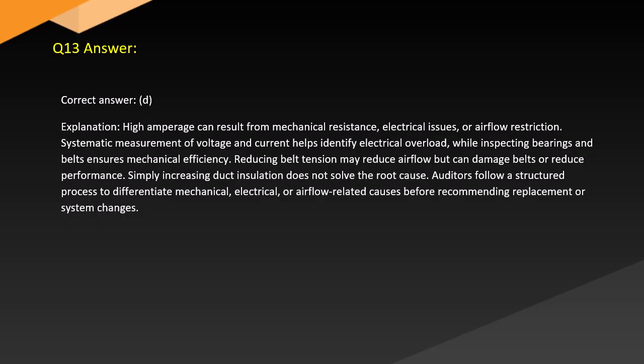Answer. Correct answer, D. Explanation. High amperage can result from mechanical resistance, electrical issues, or airflow restriction. Systematic measurement of voltage and current helps identify electrical overload, while inspecting bearings and belts ensures mechanical efficiency. Reducing belt tension may reduce airflow but can damage belts or reduce performance. Simply increasing duct insulation does not solve the root cause. Auditors follow a structured process to differentiate mechanical, electrical, or airflow-related causes before recommending replacement or system changes.